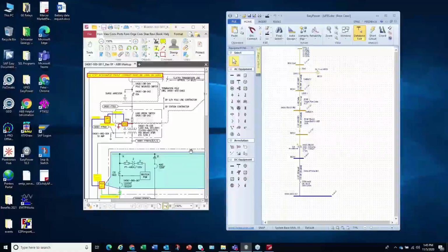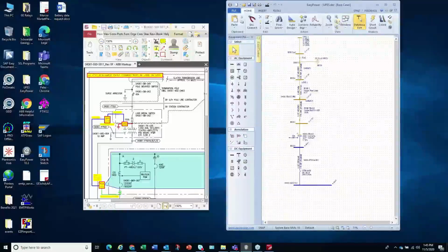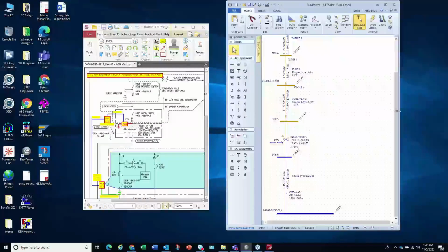Excellent. Okay. The one on the left is the one-line diagram of the system, similar to what was just discussed. There's a low voltage switchgear here. This is a retrofit, so it's an older unit fed by a 1000 kVA pad-mounted transformer, which is fed by a 12 kV overhead line. And I have modeled that in EasyPower. Let me just make it a little bit bigger here.